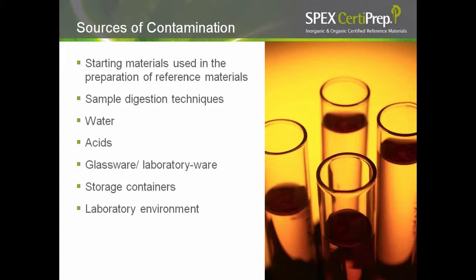In these days, analysis at low level is not limited by instrumentation. The limitation comes from interference due to contamination from elements that are not of interest. What are the sources of contamination? We use reference materials to calibrate our instruments. Starting materials used in preparation may contain trace impurities. We also use various digestion methods to prepare samples for analysis. Water, acid, and even laboratory ware can add impurities. Storage containers can leach impurities into solution. Most of all, the laboratory environment is cause for concern.